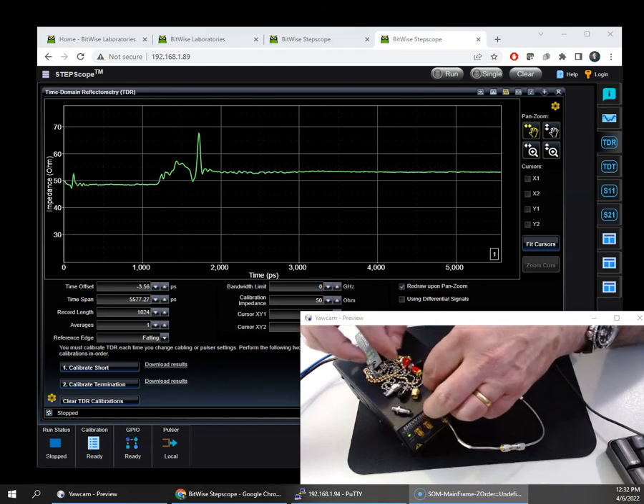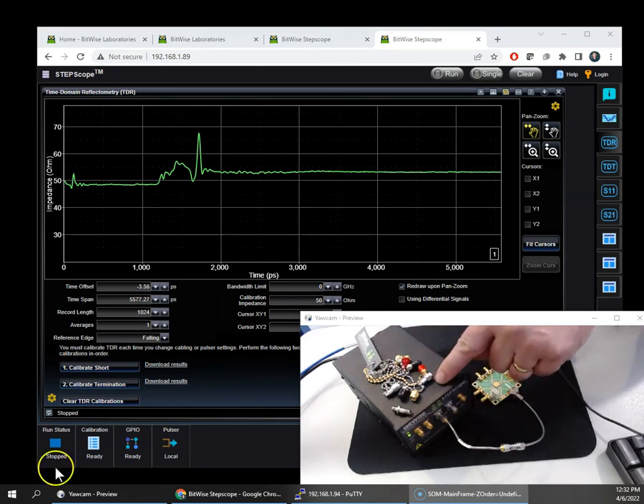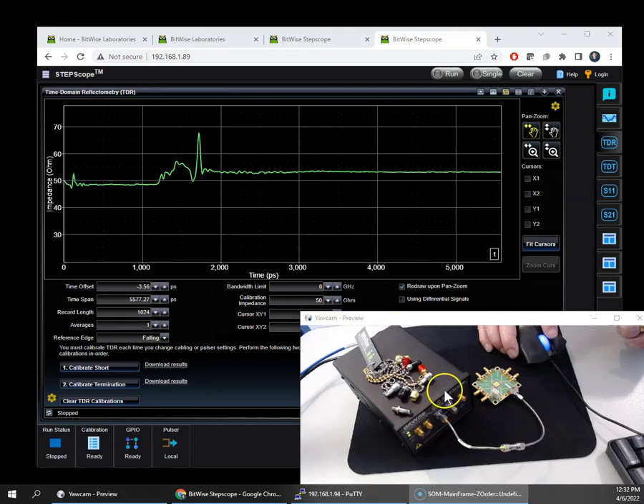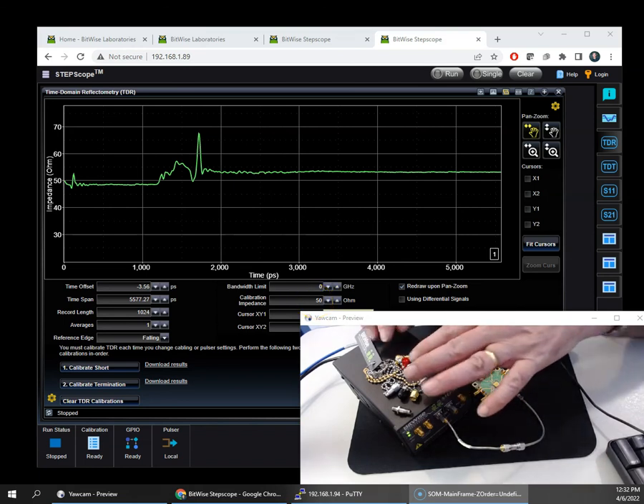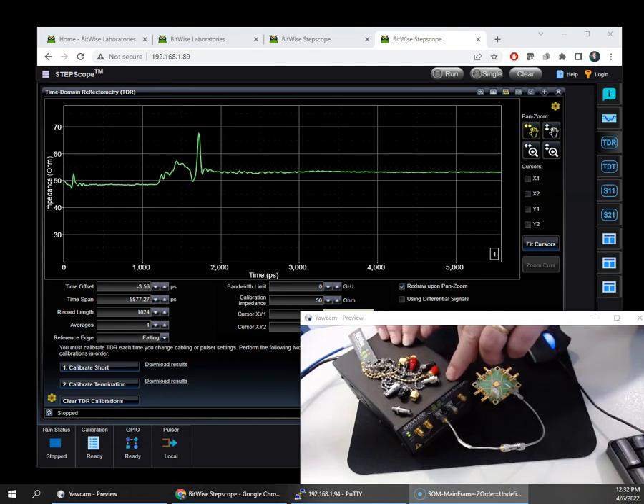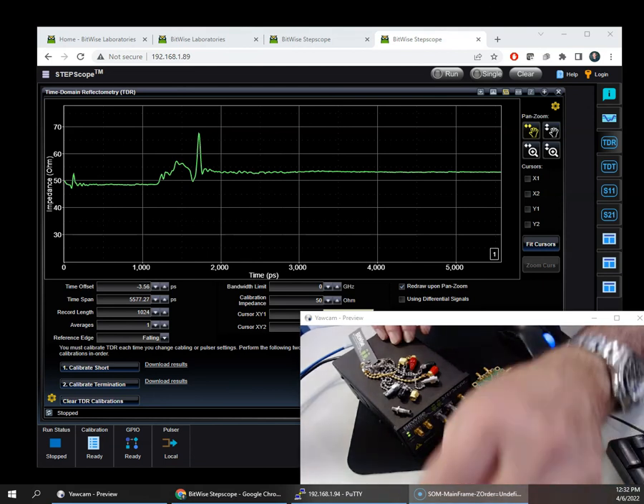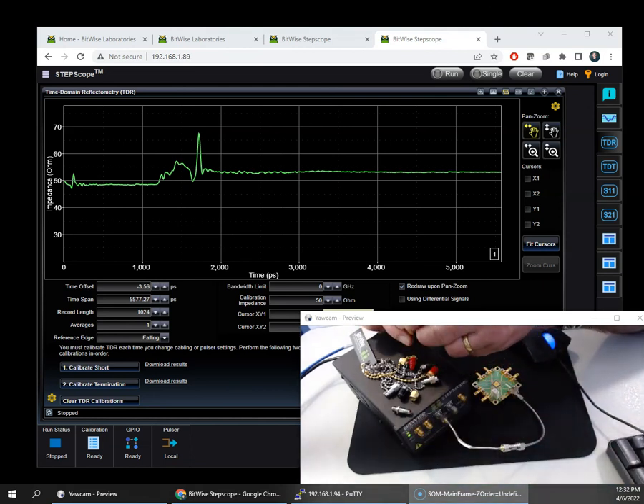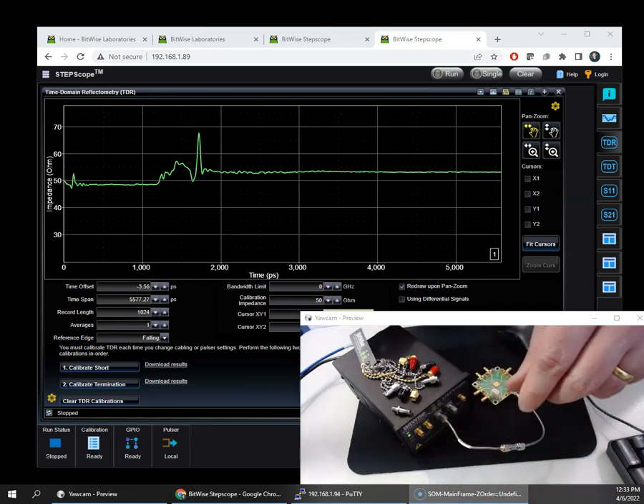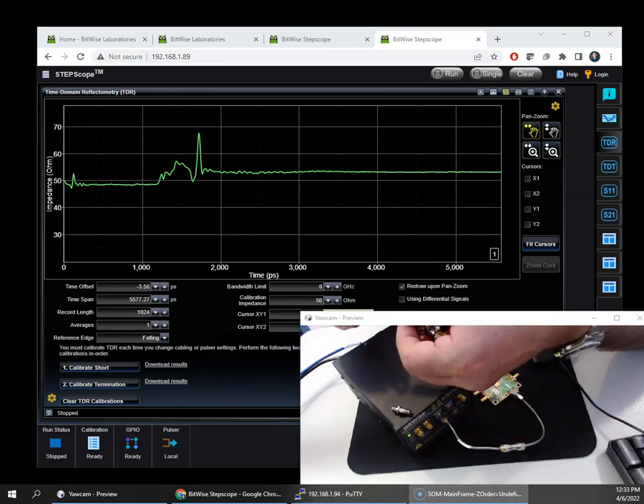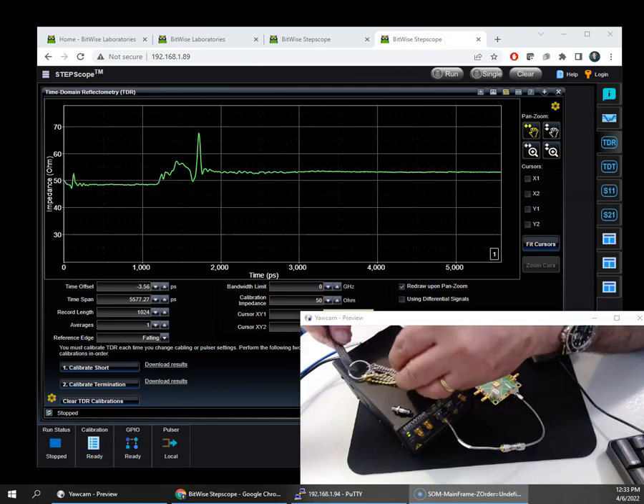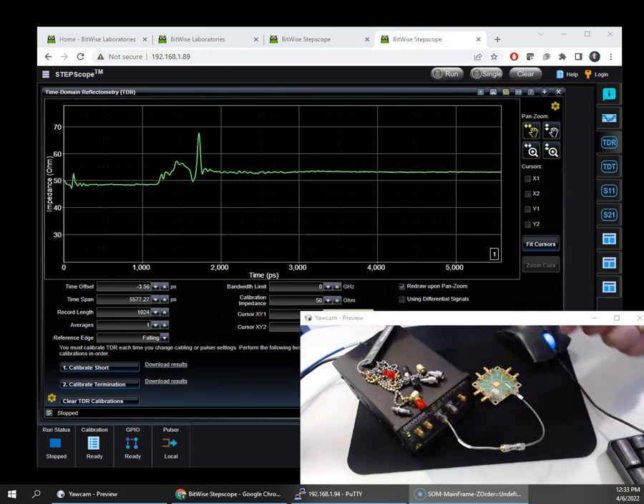And so to help with that, we actually took that into consideration in the instrument. We have a setting here called the calibration impedance. If you take an ohm meter and find that your termination is 50.2 ohms, you can type in 50.2 ohms here, and it will adapt the graph for that kind of termination impedance during the calibration. That comes in very helpful for being able to use a more cost-effective termination strategy for your measurements in labs or manufacturing environments where you might not want to have exposure to these very high-end and expensive calibration kits. The kit also comes on a nice key ring here with chains, so that you can just keep everything in one place, and you can make those kind of measurements that you need to make.